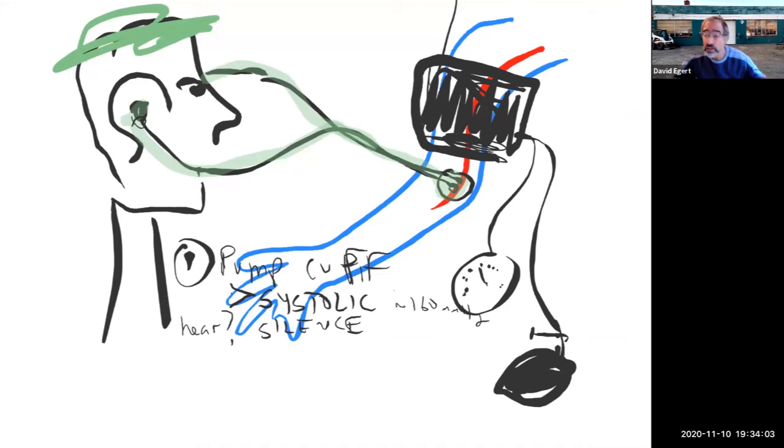At this point, you don't want to linger here because you've basically put a tourniquet on your person. And the longer they wait like this, the more uncomfortable it's going to get, having a complete lack of blood flow to their arm. So what you're going to do is turn this little needle valve. You're going to start bleeding the air out of the cuff. And we're going to see the little gauge start going down, because as the pressure in the cuff goes down, the gauge goes down.